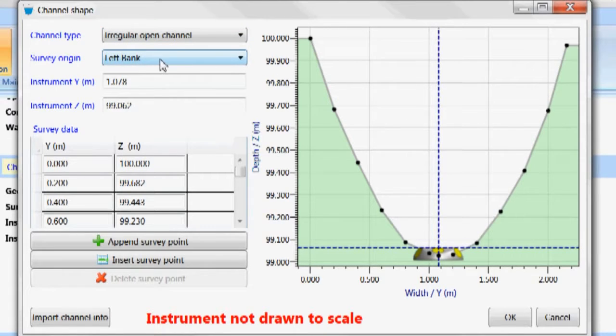We set the survey origin as the left bank or the right bank. This orientation is defined as you're looking downstream: to your left would be the left bank, to your right would be the right bank. It's important for us to tell the instrument where it is within the cross section. In this case, we installed the instrument and then performed a channel survey where we measured the actual cross-sectional area of the channel, and we measured the instrument's location in that channel in terms of its position, its width across the channel, and its elevation in the channel.